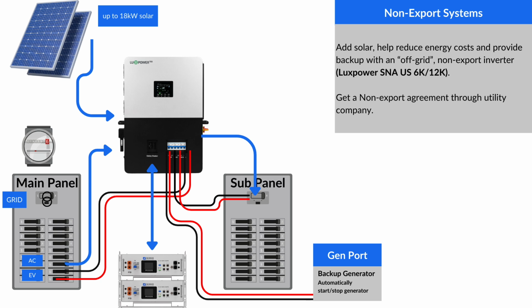You can connect these inverters to the main panel just like a large load would be, like an electric vehicle or an electric water heater or an electric dryer. But energy only flows one way. It flows into the inverter and then it flows into the sub panel or the batteries for charging. Any extra solar that's being produced that can't be stored in the batteries or in the sub panel for loads will just be clipped. And this allows for non-export agreements with the utility company, which can oftentimes be easier to obtain.